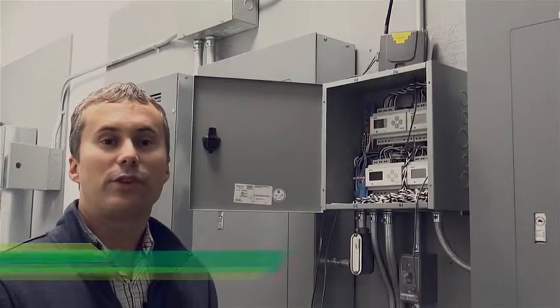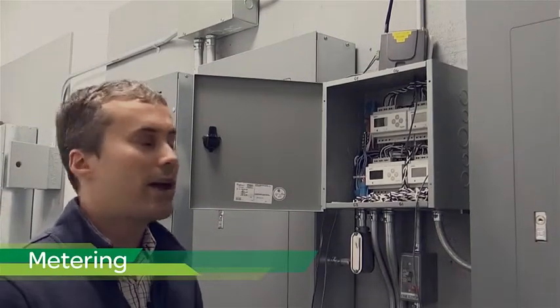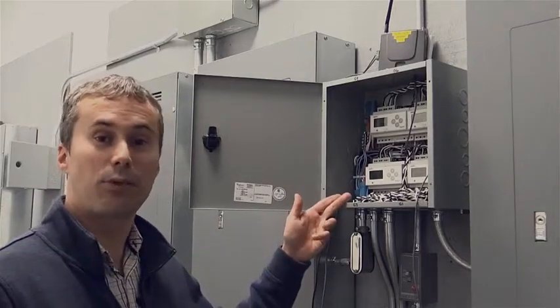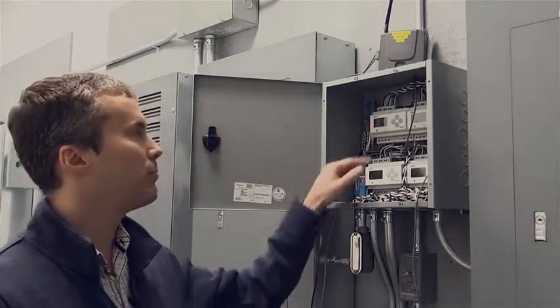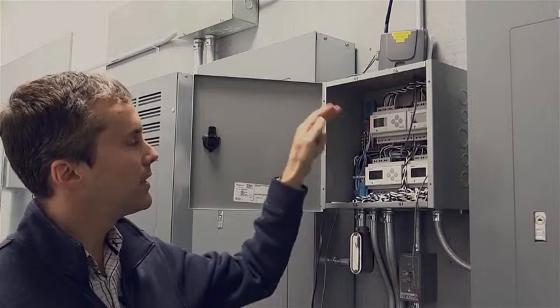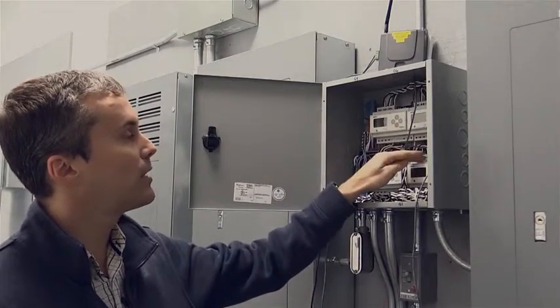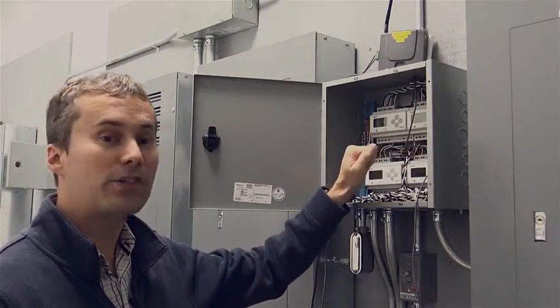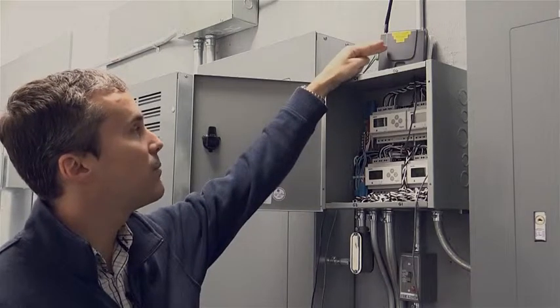The third component of our solution is power metering. Via power meters and split core CTs, we're able to measure main load, HVAC load, lighting load, and other loads, transferring this information via Modbus RTU back to the NPM-UN.